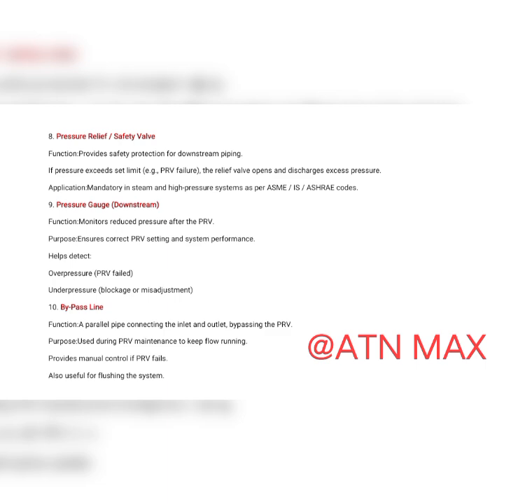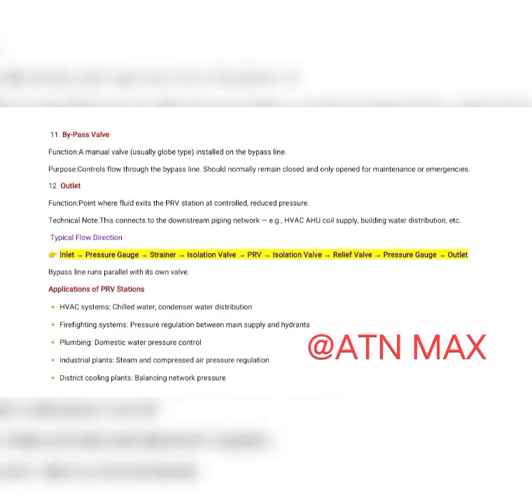10. Bypass line. Function: a parallel pipe connecting the inlet and outlet, bypassing the PRV. Purpose: used during PRV maintenance to keep flow running. Provides manual control if PRV fails. Also useful for flushing the system. 11. Bypass valve. Function: a manual valve, usually globe type, installed on the bypass line. Purpose: controls flow through the bypass line. Should normally remain closed and only opened for maintenance or emergencies.